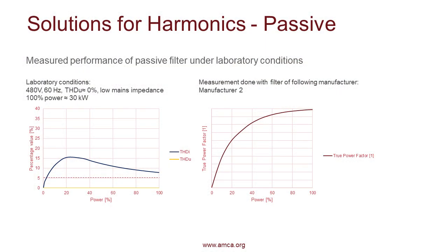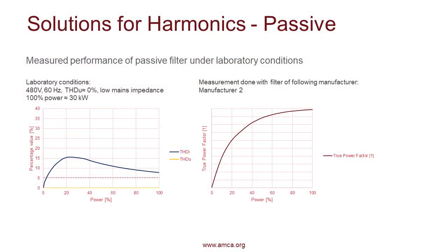We can look at another manufacturer, and now we notice there's a drastic difference. Now, at partial load, we can see our total harmonic distortion current has increased above 15% at a partial load. But our true power factor at 100% load is now closer to that 1. So maybe this is a good solution for a system that's running at 100% load. Your THDI is still less than 10%. Your true power factor is close to that 1. So this might be a good solution. So passive filters are really good, but they have different interactions with different equipment.